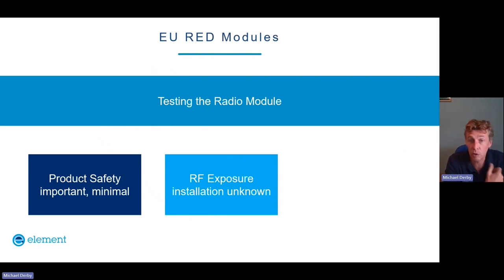RF exposure, well, you don't know the end installation, but an assessment is usually performed. So for example, if it's less than 20 milliwatts, you could easily say that a SAR assessment would not be necessary, and you can easily demonstrate compliance at greater distances. But if the power is more than 20 milliwatts, you could perform calculations to demonstrate what sort of distance it could be used at.